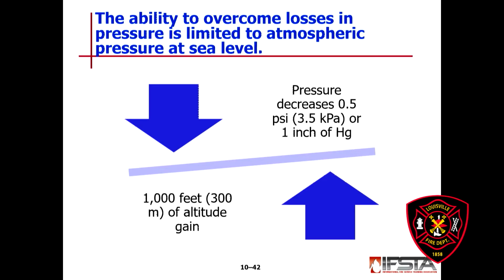And then the ability to overcome losses in pressure is limited to the atmospheric pressure at sea level. We are pretty much at sea level here, so we don't have to deal with this too much. But those cities that are at higher altitudes have to do some additional calculations to figure out how well they're going to be able to draft from a static water source. Because the same atmospheric pressure of 14.7 must overcome elevation pressure as well as any friction loss that we talked about in the last slide. Then, if you increase the height of that lift, that's also going to decrease our total pump pressure.